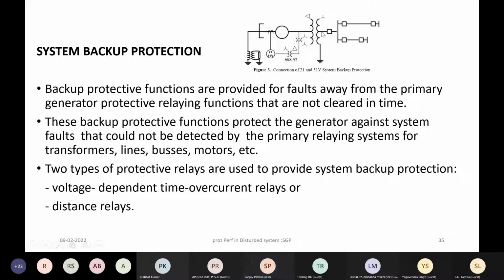Then the switchyard and the outgoing lines fall in that. Any fault taking place either in the switchyard or on the outgoing transmission line also needs to be covered as a backup protection on the impedance relay. So this impedance relay can reach up to, say, 50% of the shortest line which is there.